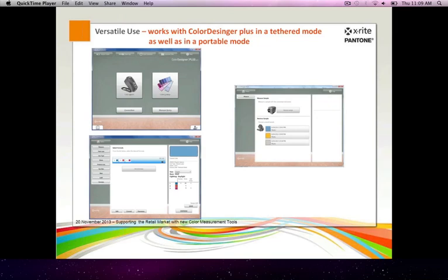So depending on the use, you can either use the instrument to measure samples directly at the instrument, or you can recall, as we see it on the right-hand side, samples from the field and transfer them into the color designer to either search for a solution with a database or calculate a new formula, which can be then provided to the dispenser or can be saved into the color designer system.